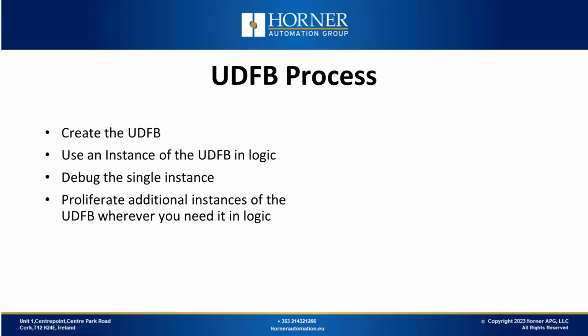Now we'll look at the process for using UDFBs. First, create the function block. Use an instance of it in your logic, and debug it to ensure it's free of bugs. You want to confirm its reliability before replicating it. Once proven, proliferate the code by adding additional instances in the same project or saving it for future projects. Creating a UDFB involves naming it, assigning input variables, internal or private variables, adding output variables, and defining the logic. If you discover the need for more variables while creating the logic, it's an iterative process you can perform.